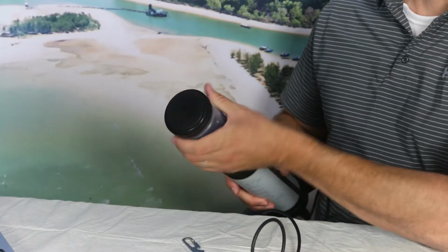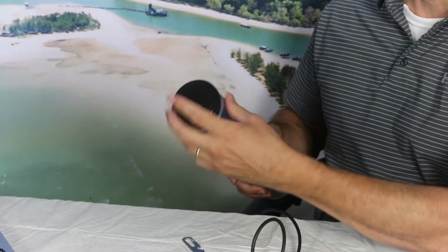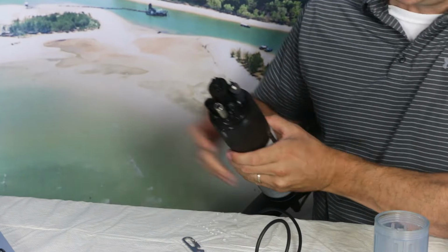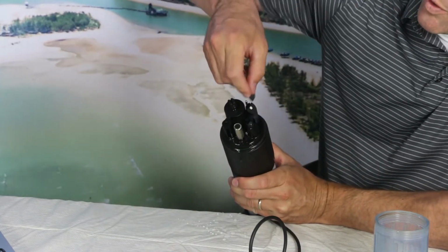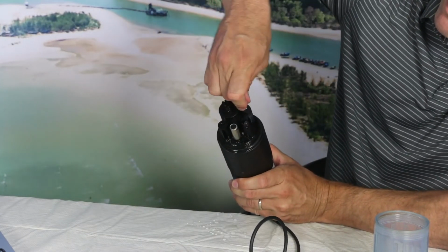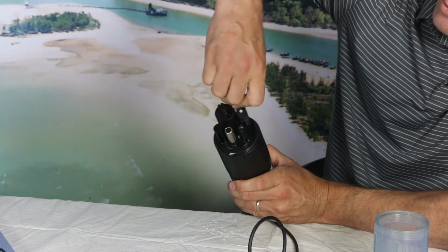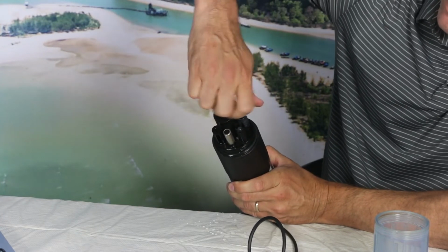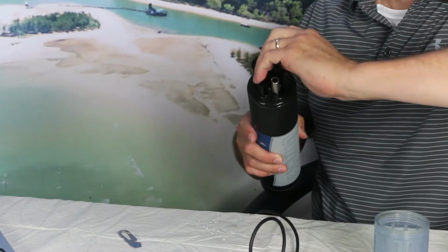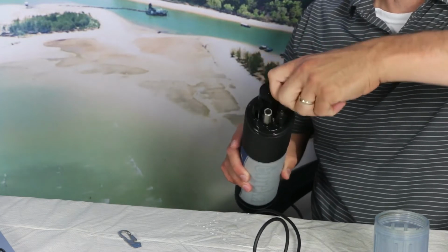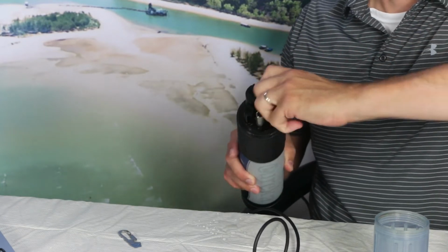If you haven't replaced your reference electrolyte recently, now is the time to do it. This is a good time to replace the electrolyte solution before you calibrate your pH sensor. So to replace our reference electrolyte, we're going to remove the calibration cup. You can use a coin or a flathead screwdriver to remove the reference cap, and we're just going to dump out the solution that's in there and replace it with new solution.